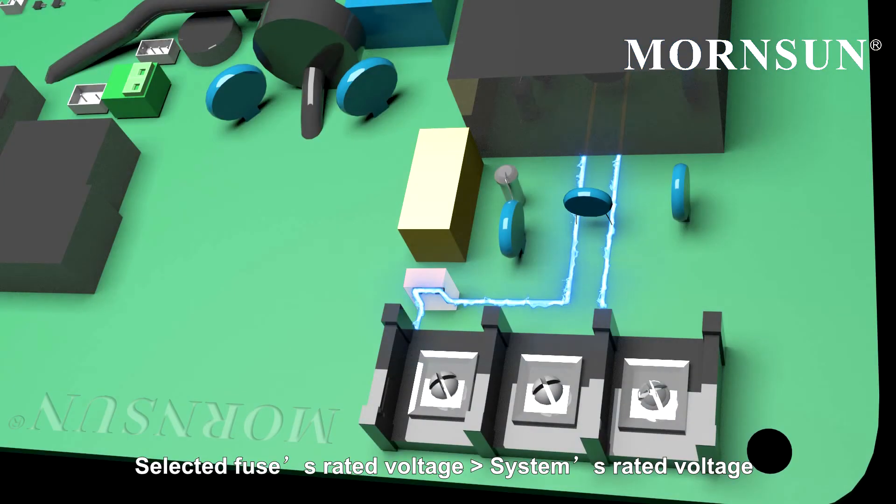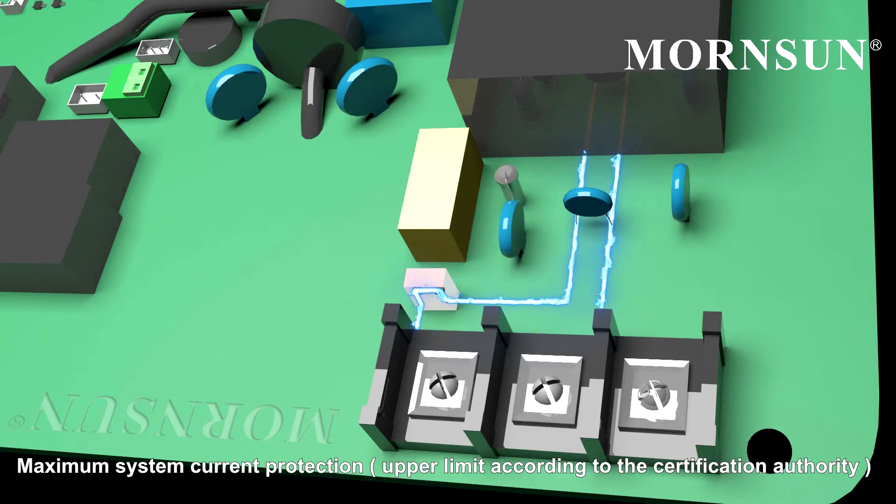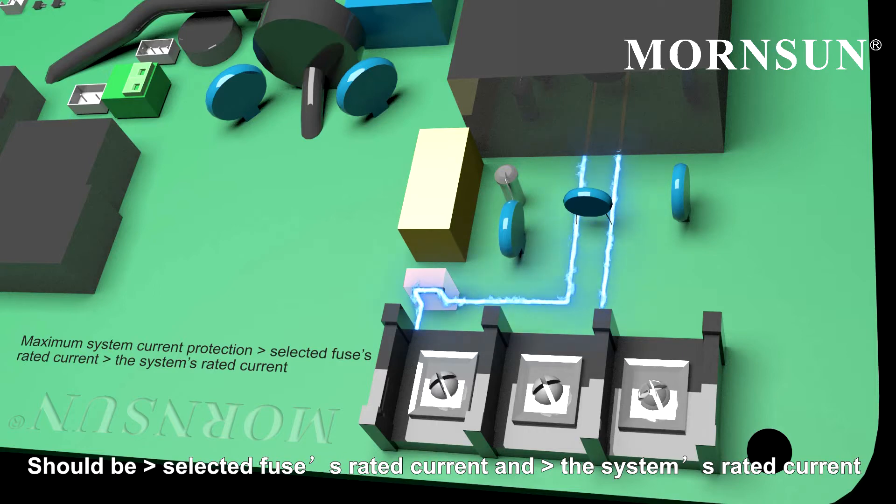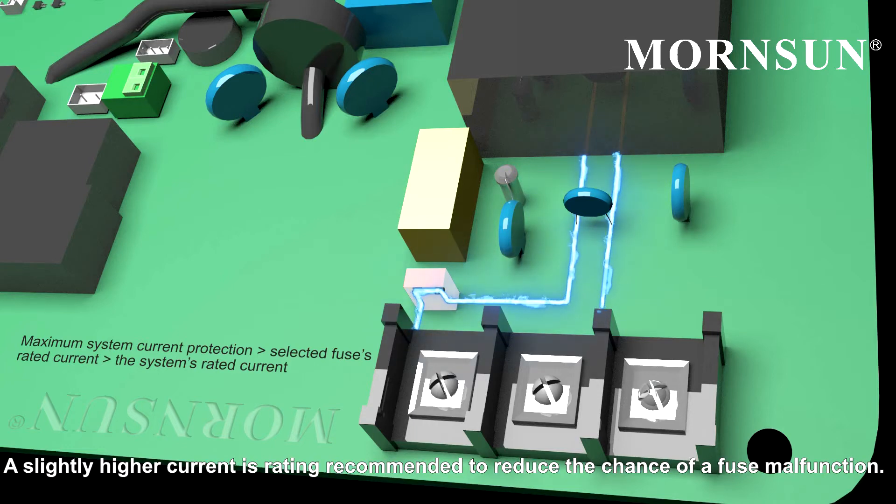Selected fuse's rated voltage should be higher than the system's rated voltage. Maximum system current protection, the upper limit according to the certification authority, should be greater than the selected fuse's rated current and greater than the system's rated current. A slightly higher current rating is recommended to reduce the chance of a fuse's malfunction.